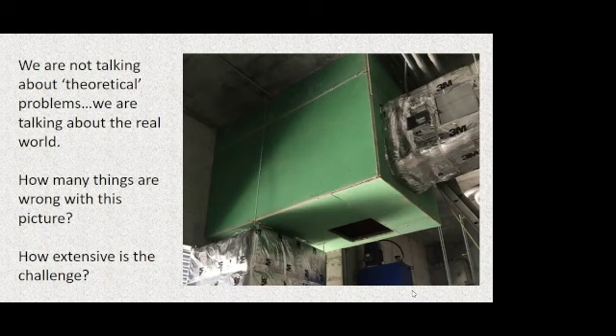We also see that that duct smoke detector doesn't have a 2-hour cover. I need the duct detector, but I can't just cut away the fire rated assembly to put it on. If I can see accessories, actuators, duct sensors, pressure sensors, duct smoke detectors, anything that we're carving away to attach to the duct needs to be protected. We violated the fire resistance. We need to put a 2-hour cover on that. And the 2-hour covers are not just more insulation slapped over the accessory. It needs to be accessible for service and maintenance. It needs to be within its operable temperatures.